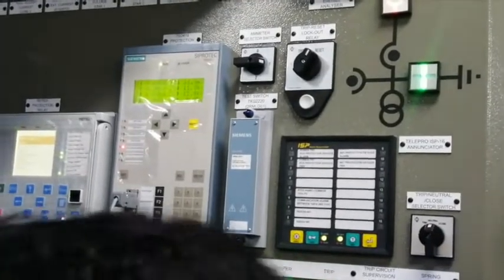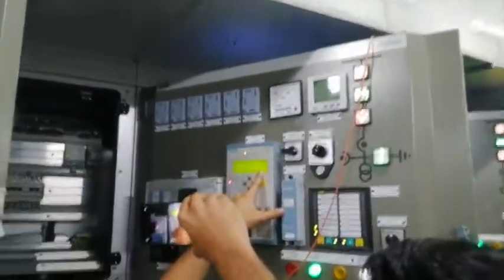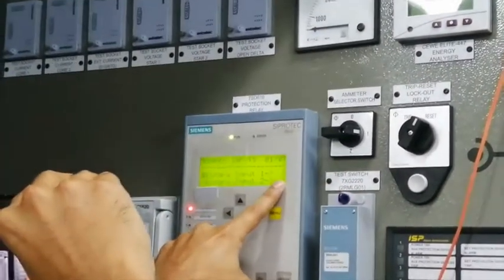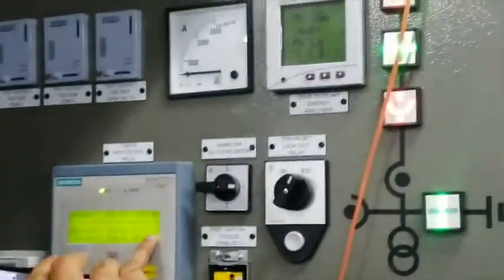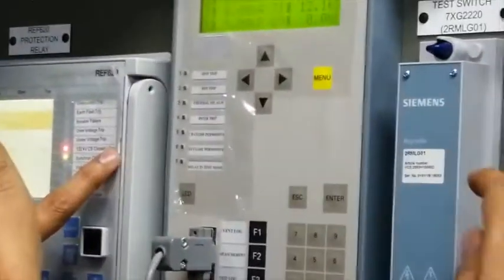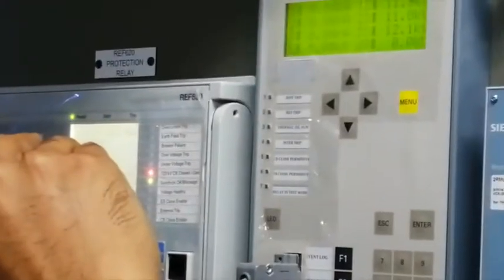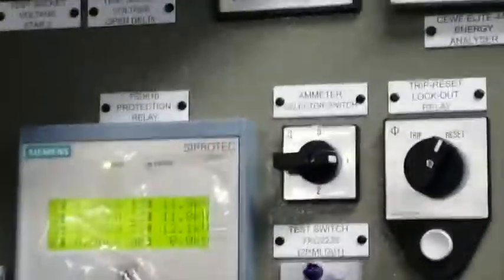Now we will retry the test by inverting the signal on the 132kV side. We configured binary input 1 of the 132kV Siprotec relay as the permissive signal. By removing this signal using the test plug, binary input 1 goes to 0. On the 11kV Siprotec relay side, the LED is now red, indicating 132kV CB is open and we are not allowed to close the 11kV breaker. Binary output BO3 of the 11kV Siprotec relay going to the ABB relay is now 0.